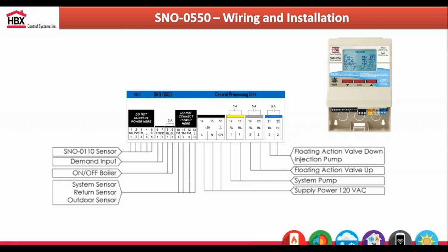With all our 550 controllers, it's very straightforward. We use a lot of dry contacts on there. Those dry contacts are rated for 240 volts at 5 amps for each relay. Your outdoor sensor is a 5-wire sensor. 4 wires are color coded, and each sensor wire has a designated terminal to go in.